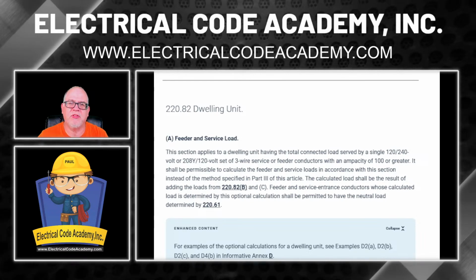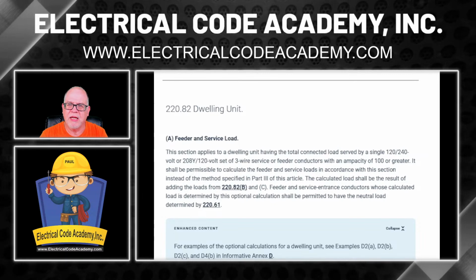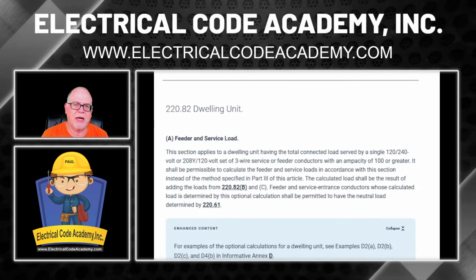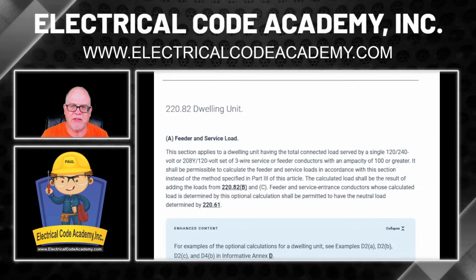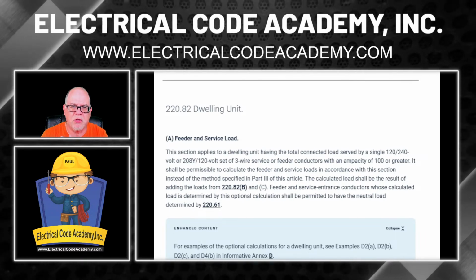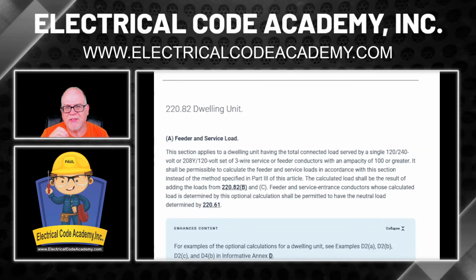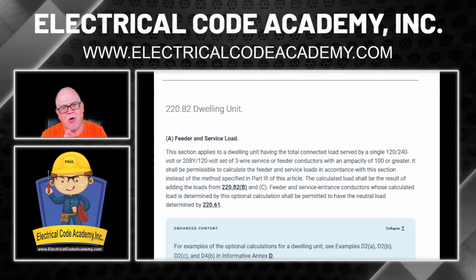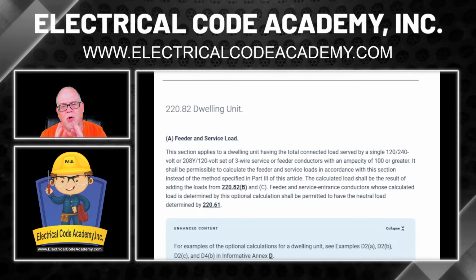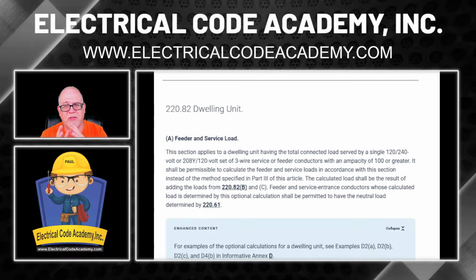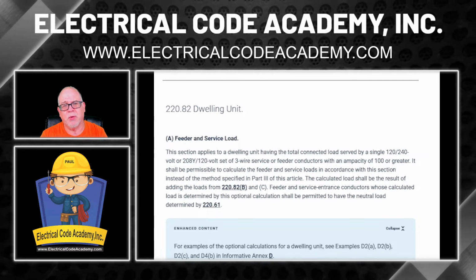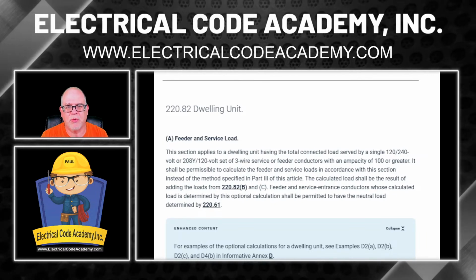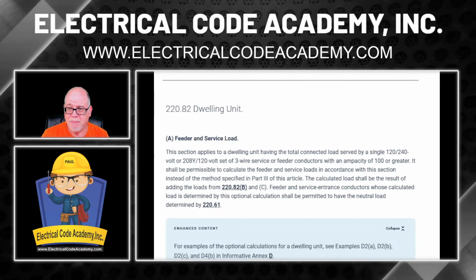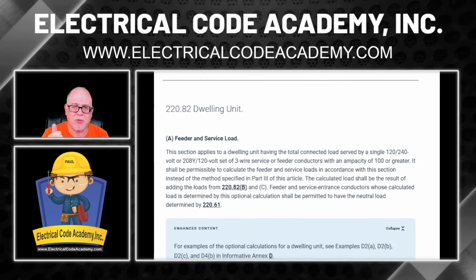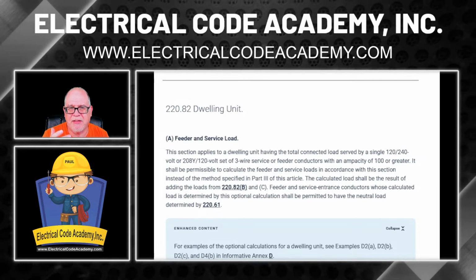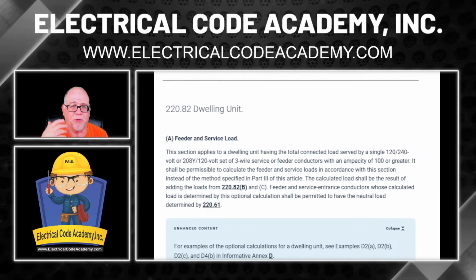All right. So what you see is it talks about feeder and service loads, and it tells us that since it's a dwelling unit, we're going to follow this optional method if it's a 120/240 or a 208Y/120. Well, even though it was 230 and 115, we know that the nominals are 120/240. So we know that we're dealing with a single phase 120/240. But that's not the most important part here. This is broken down into an A, a B, and a C. B is the one that deals with the 3 VA per square foot, talks about adding up all the nameplates, the first 10,000 at 100% and the remainder at 40%.